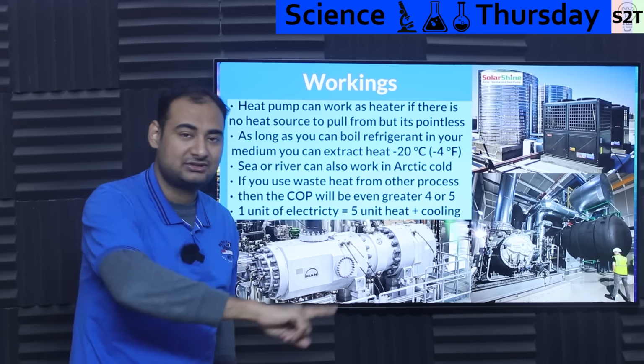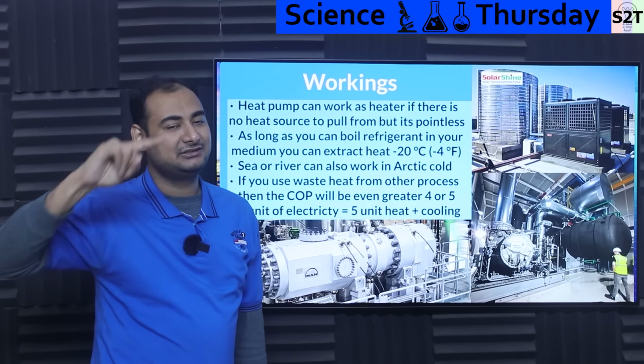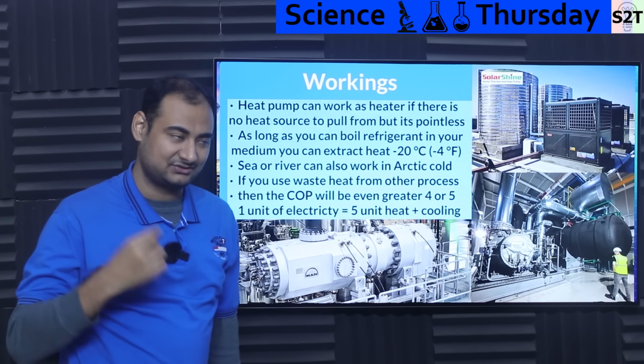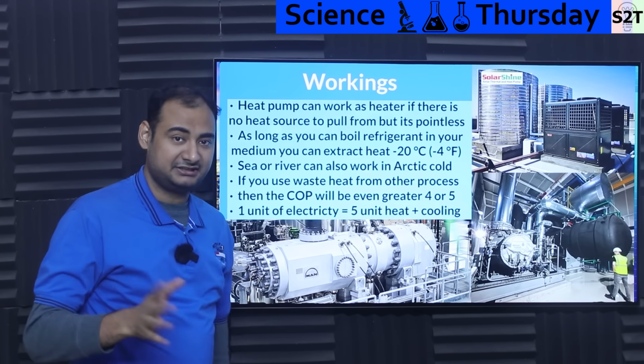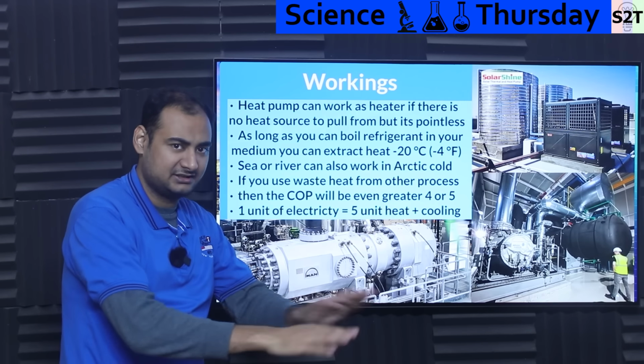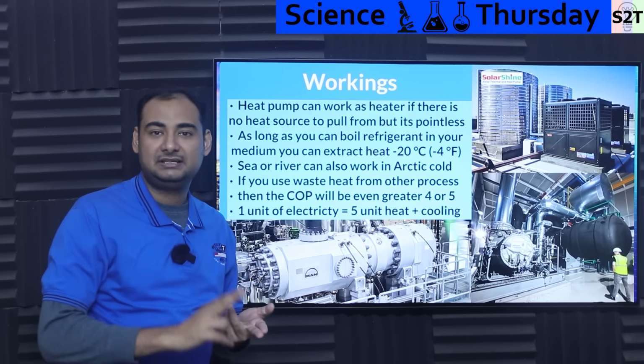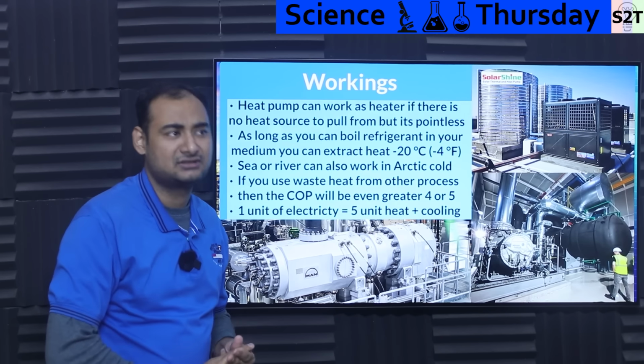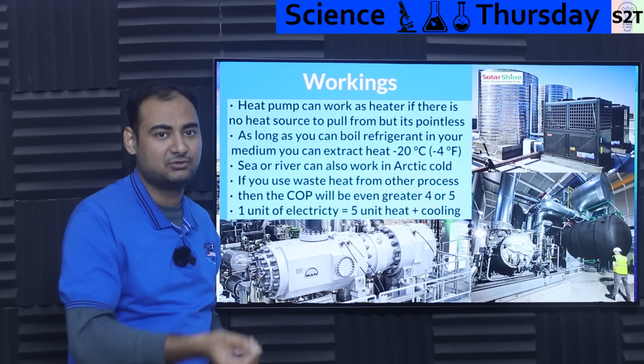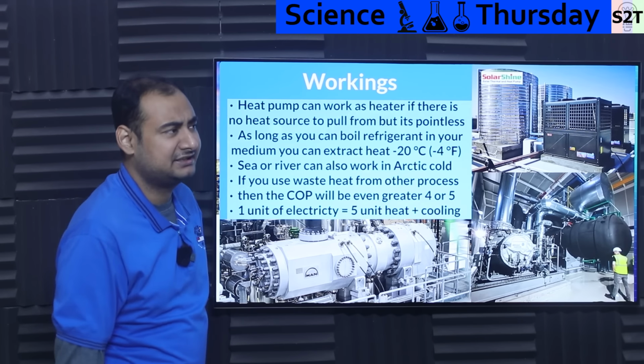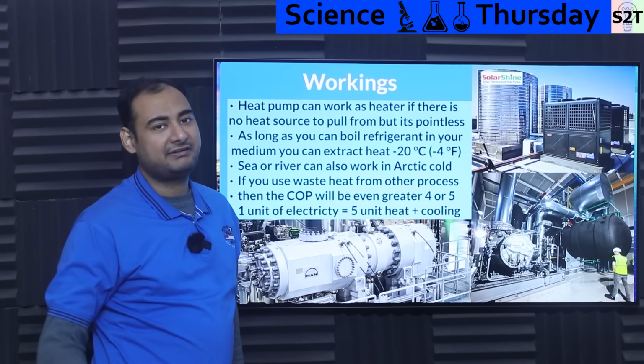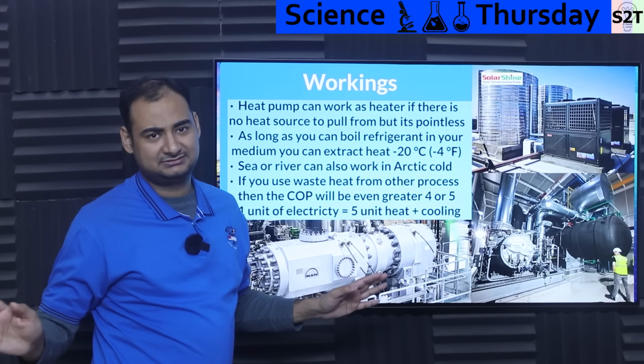Of course, because you're trying to lift so much, trying to do that in one jump would be unwise because your COP will go down. But it can be done. It as a source of heat, it's good, it's done. UK is also trying that. So sea and rivers, as long as there is liquid and it's not almost at freezing point, you're good. If the liquid, especially the sea, is 4 or 5 degrees Celsius, you're good.